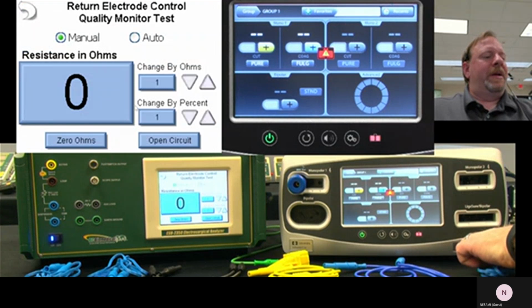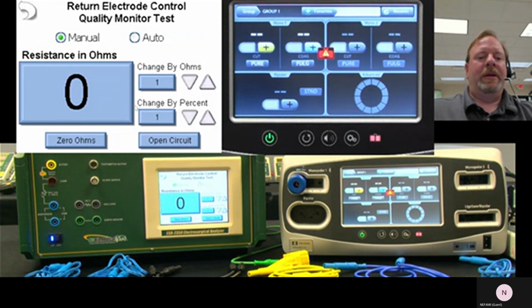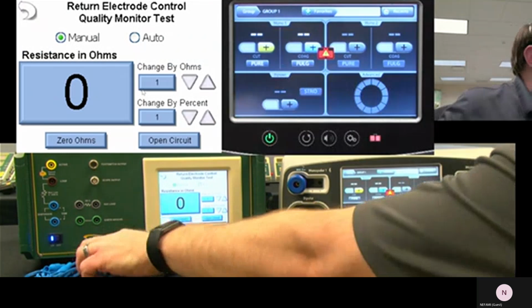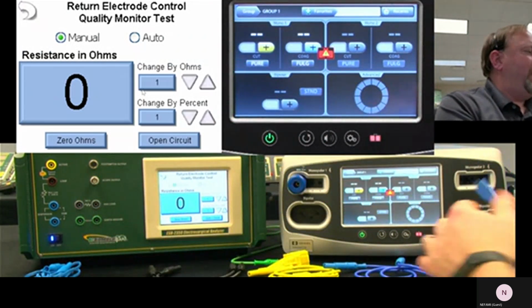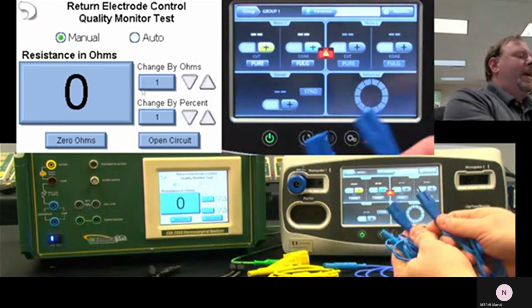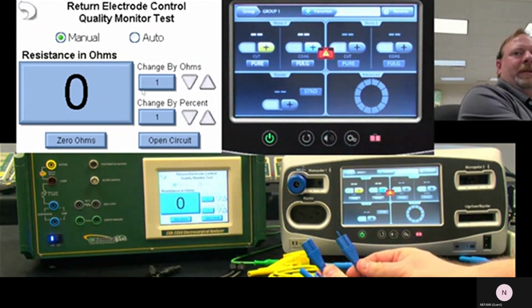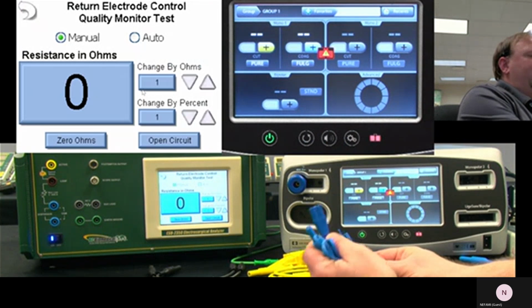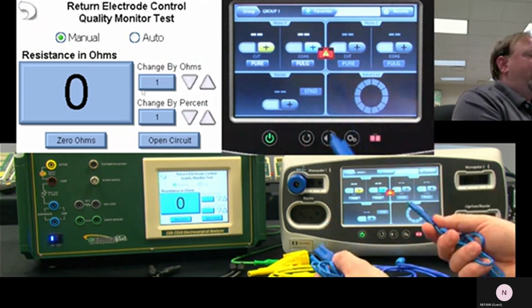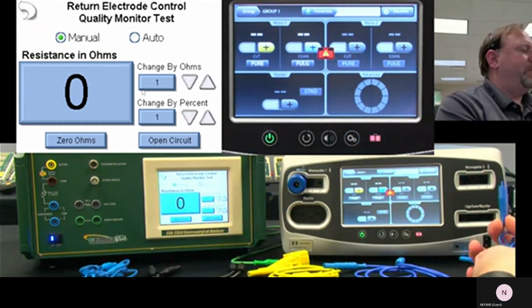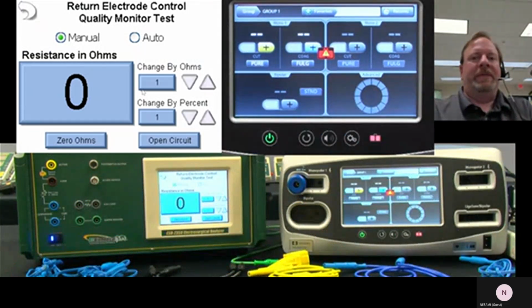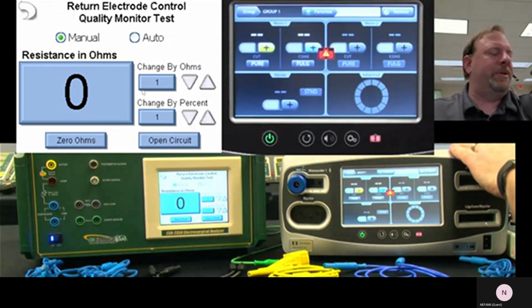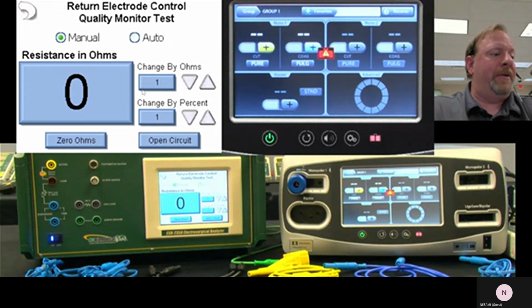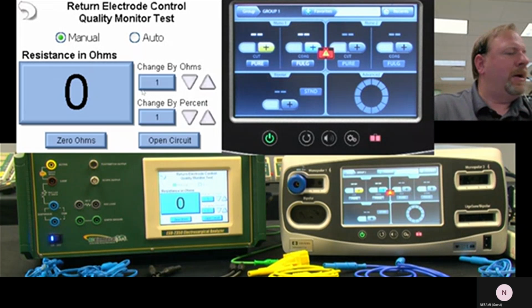The REM test, that's measuring the return electrode monitor. REM, ARM, CQM, different manufacturers call them different things. But the main thing to note here is that we have two cables that come with the 2300. And most generators identify, I'm trying to get this in a good visual spot here, most generators identify whether you have a split or a single pad based on this pin. So the pin that's here, that identifies that you have a split pad, and the generator then measures the resistance between the electrodes to make sure that it's valid. Now, the Covidien FT10 and the Force Triad, they always use split pads. They don't allow you to use a single pad. So that makes it easy for that testing.